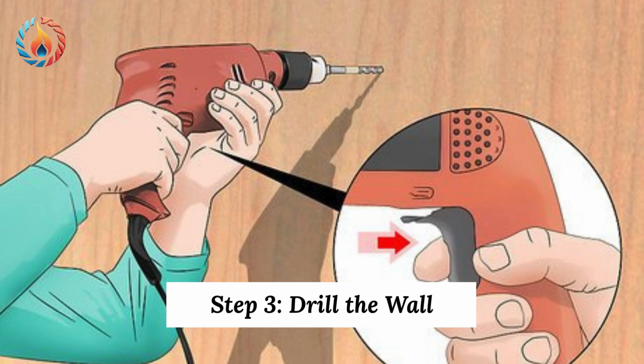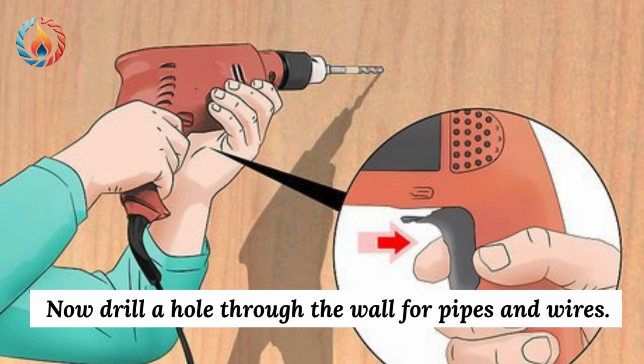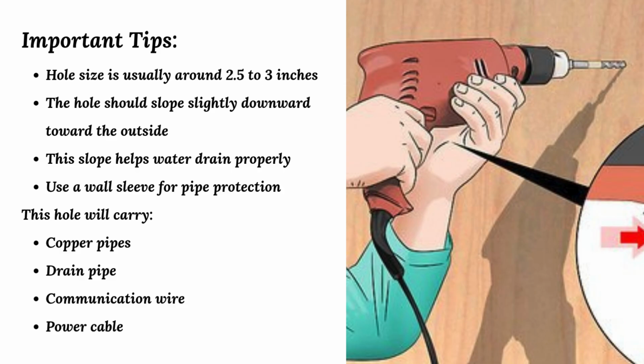Step 3. Drill the wall hole. Now drill a hole through the wall for pipes and wires. Important tips. Hole size is usually around 2.5 to 3 inches. The hole should slope slightly downward toward the outside. This slope helps water drain properly. Use a wall sleeve for pipe protection. This hole will carry copper pipes, drain pipe, communication wire, power cable.